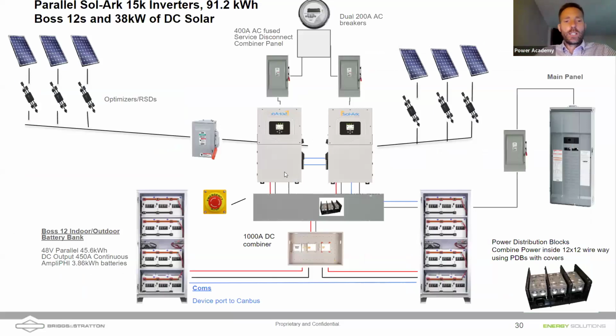So here's another example showing this with a couple of Boss 12s. I'm showing an example of 2 Sol-Ark 15Ks paired. This will give you up to 400 amps of service. Remember, I said you can parallel up to 12 of these 15Ks. I'm showing here these are optimizers or rapid shutdowns on the panels. If you're doing rooftop mounted solar, you're required to have rapid shutdowns there.